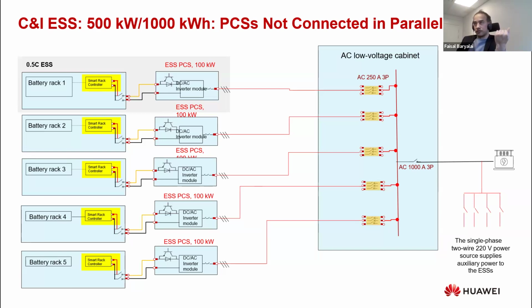But of course, 250 amps is the moderately recommended breaker for one PCS. Okay, but you can use 155 also if you want to limit that. Yes, 155 could still work for 100 kilowatt. But in the manual for 400 volt, there will be some short time that the PCS will have 120 kVA. And for that, 173 is recommended as the maximum circuit breaker capacity.